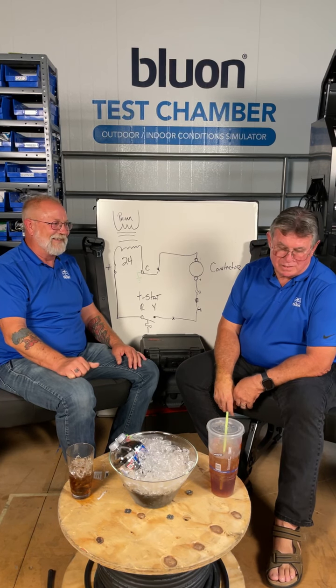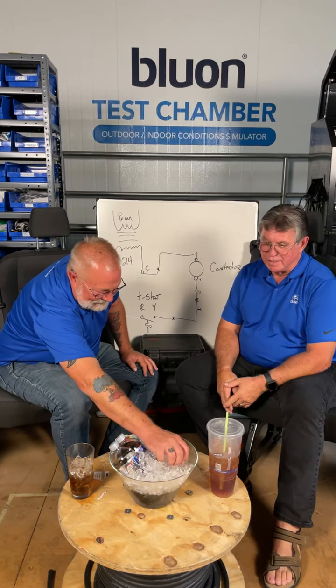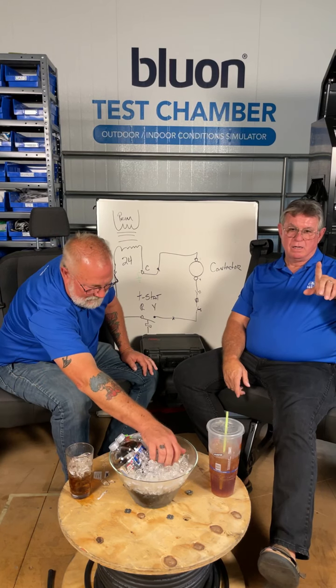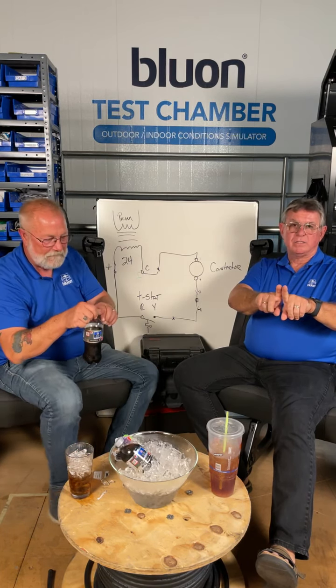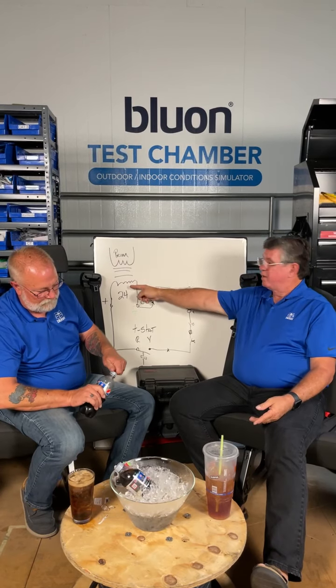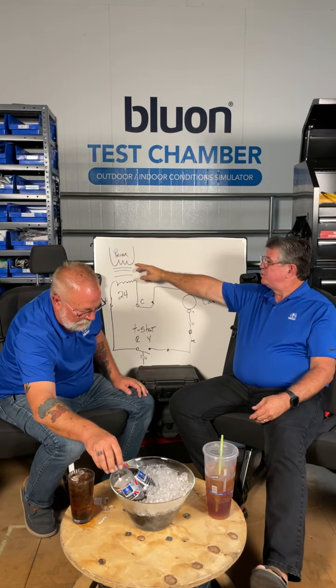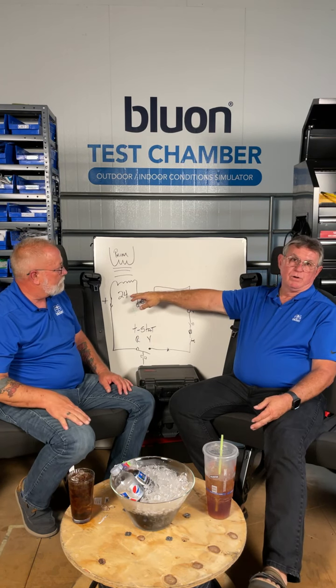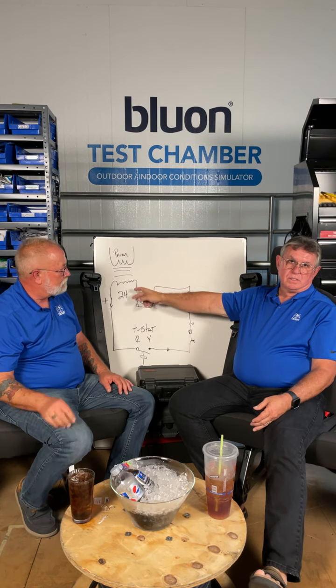Well, let's hit a couple things real quickly since you opened that door. If I take a low voltage wire or a low voltage cable and I put it right next to some high voltage wires, you can get what's called inductive coupling and capacitive coupling, which means that the two wires are now acting like a primary and a secondary on the transformer. So you can induce a voltage from the high voltage wire into your low voltage wire. So whenever you're running low voltage wires, you want to try to keep the high voltage separate from the low voltage. And if you have to cross the wires, do it at a 90 degree, because now the area that's up next to it is very small. So you're going to have a lot less of that problem.